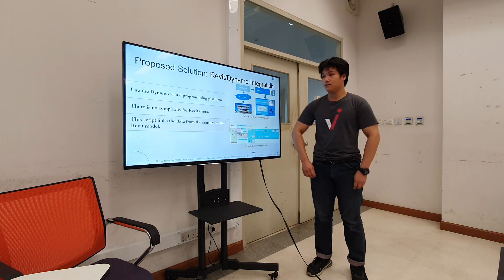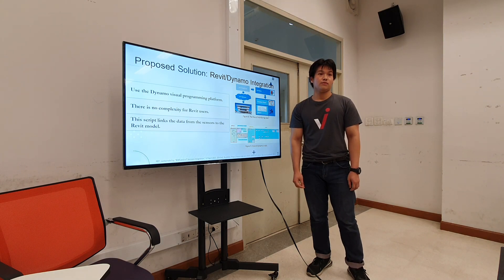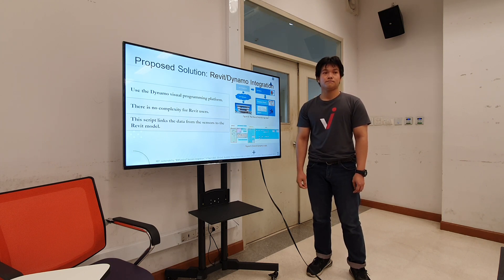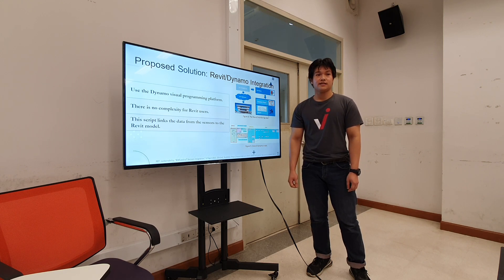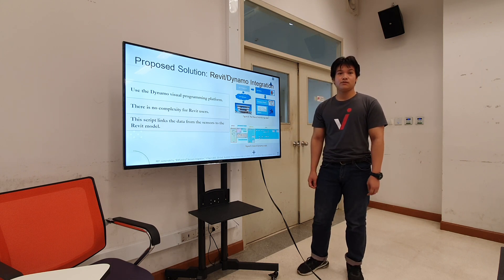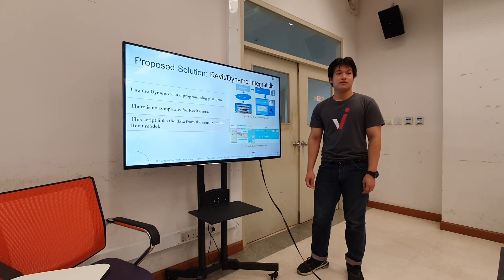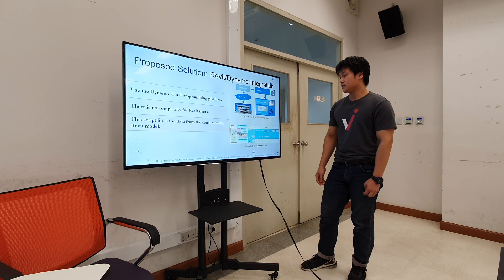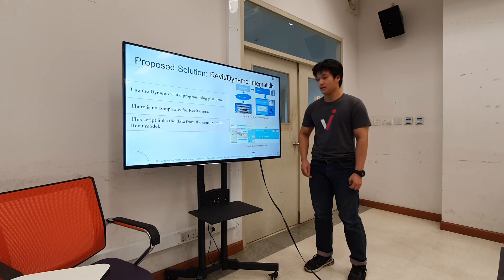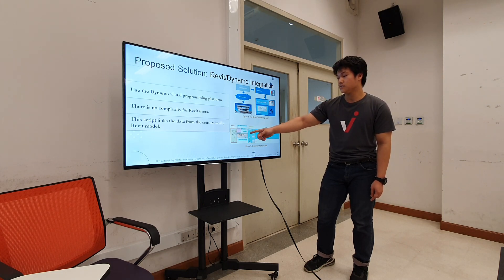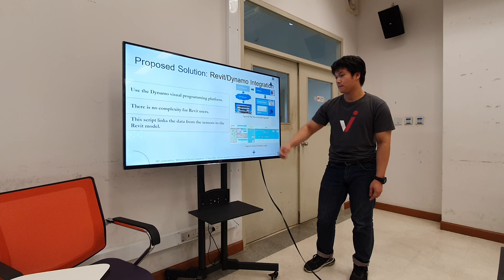Regarding Revit and Dynamo: in order to integrate BIM and IoT technology together, visual programming such as Dynamo is needed to enable dynamic and automatic data exchange between the sensors and the model. This reduces complexity for the end user at each site. As shown in figure 9, the overall Dynamo script contains steps to build and execute a URL request, handle the response, and write shared parameters to the model.